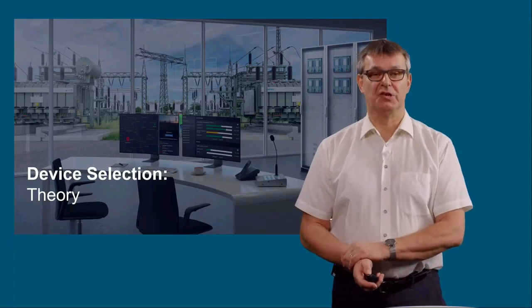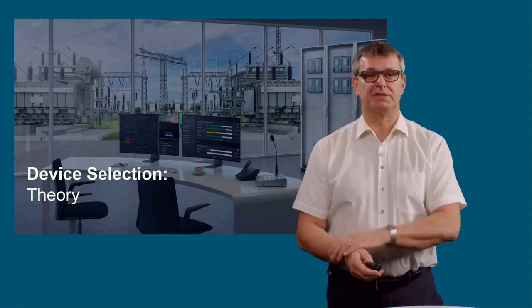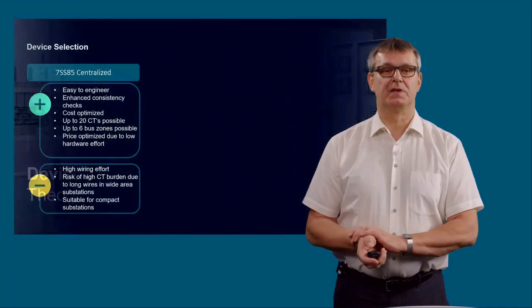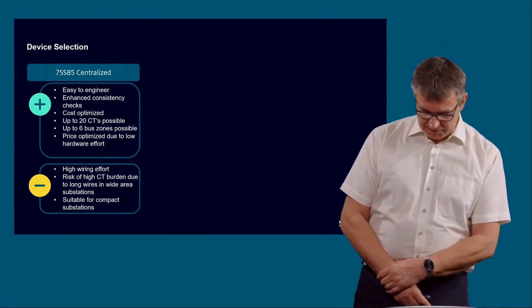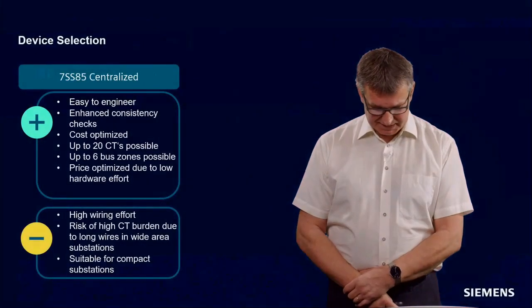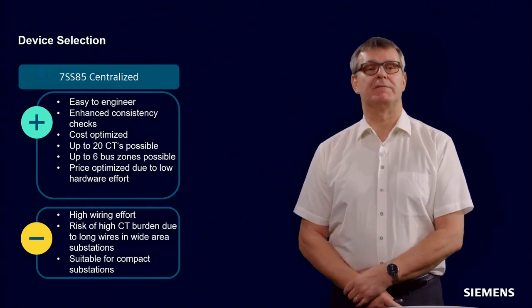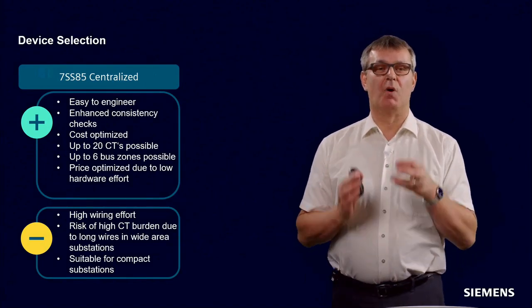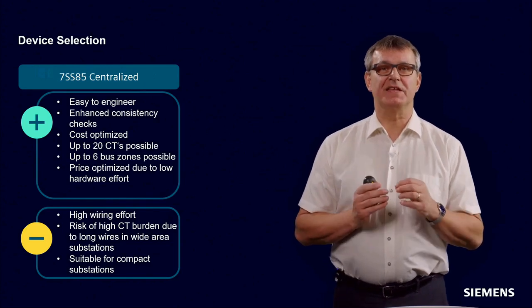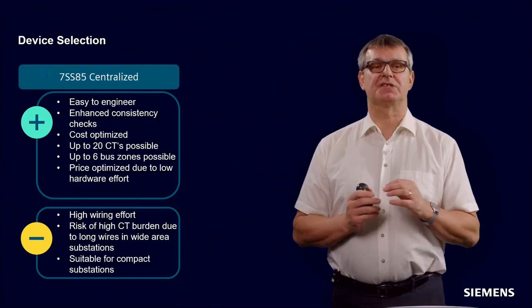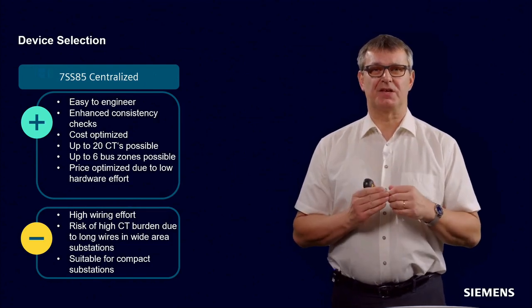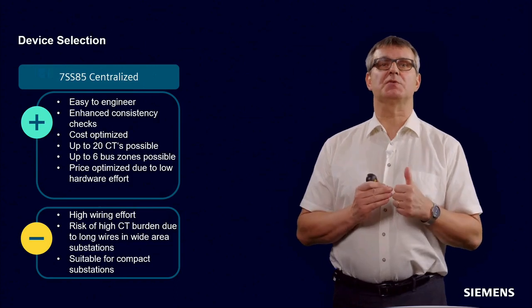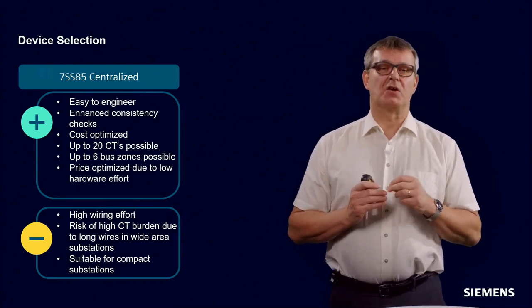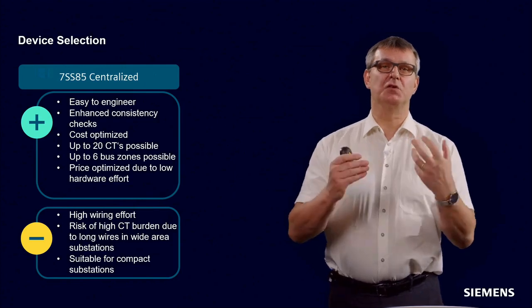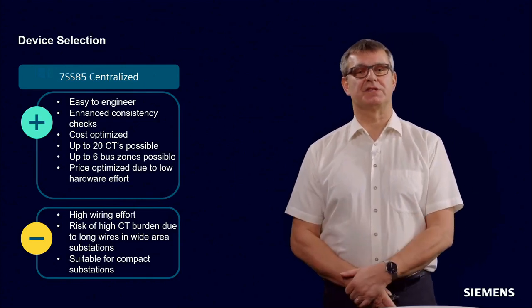Okay, let's start. Device selection theory. The practical part will afterwards Nina show to you. Before I go into details of how to configure the correct device, a small wrap-up: what are the advantages and what are the disadvantages of the three basic device types, the centralized busbar protection, the IEC 61850 compliant distributed busbar protection, and the full distributed busbar protection, the successor of the 7SS52.